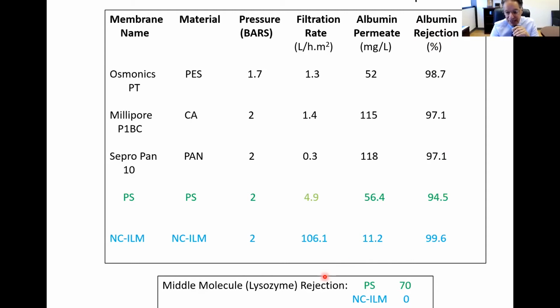It also has better, we use lysozyme to test its ability to reject the permeation of middle molecules. There's a number of middle molecules. Lysozyme has a molecular weight of 14,300 daltons. Beta-2 microglobulin, one of the hypothesized uremic toxins, is around 11,800. Light chains are around 25,000 daltons. So we use lysozyme as a molecule that's roughly in that same category as far as size. And it really lets the lysozyme through. The rejection is 0 compared to the polysulfone membrane that we had made initially. So we're pretty hopeful that this membrane will also have favorable characteristics as far as being able to get rid of some middle molecules. We'll see.